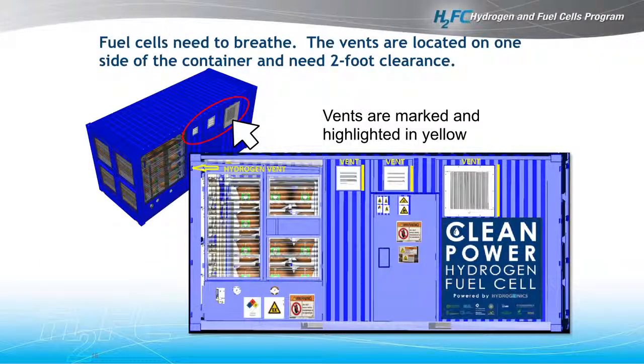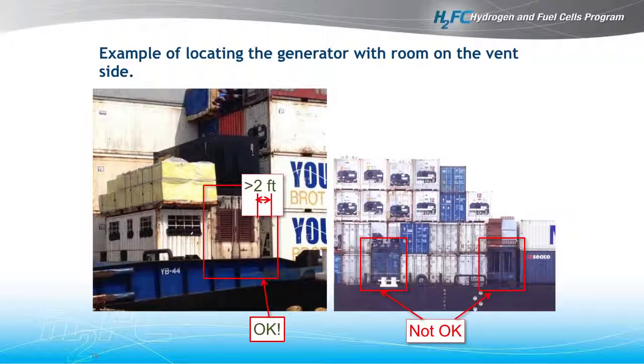The fuel cells themselves need oxygen from the air in order to function, so they use hydrogen from the tank and oxygen from the air to generate electricity. So there does need to be some clearance in the air intake, which is this vent here. And so the recommendation is the 2-foot clearance on that side, in terms of the handling for those that will be moving these around and stacking things around it. The vents, and you'll see this diagram again, will be clearly indicated with some bright colored tape or paint. And again, the hydrogen vents are at this end.